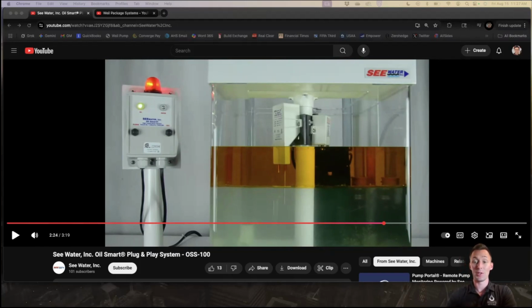Historically, there were oil separators that were in line. There was also a system where you had two solenoids where you would push the oil into a containment tank, and we haven't seen that for a number of years. And you can see that. Please go check the plumbing code wherever you are. Make sure this all works. But this is almost all of what we sell nowadays, so that's what we can speak to.